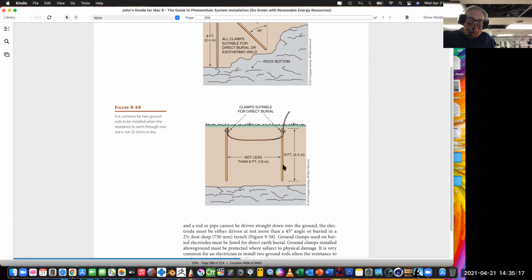Say you don't like this, so if you want, you could just keep putting in grounds all day long. It ain't going to change anything. But what you need to recognize is it's common for 2 ground rods to be installed when the resistance to earth through 1 rod is not 25 ohms or less.